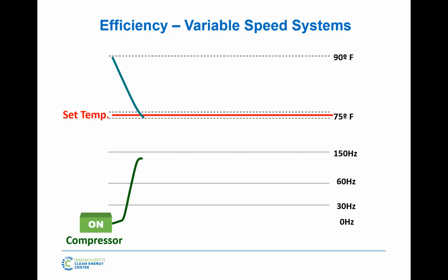It'll turn it on, then as it gets close to set point, it's going to start ramping down the compressor a little bit to a point where it's going to stabilize, right? 60 hertz is the usual frequency of the grid. This one might stabilize at around 45 hertz. That's the inverter, right? Which means your expansion valve is slowly zoning in, dialing in exactly what your space needs for the next couple hours, and it changes, and it keeps your room temperature very smooth.